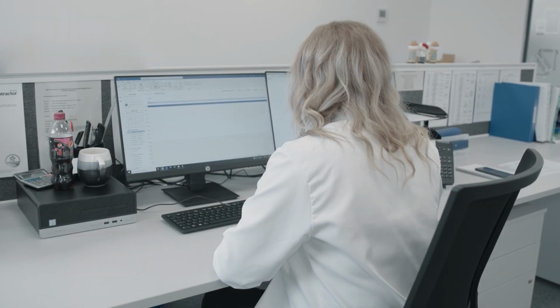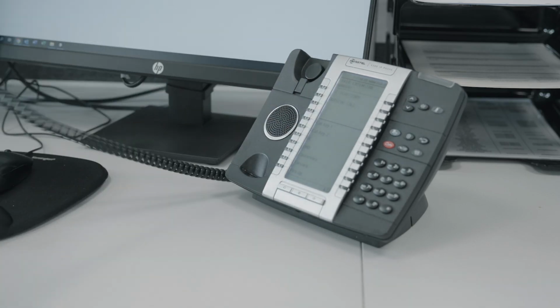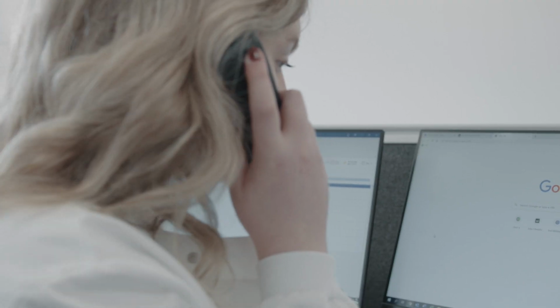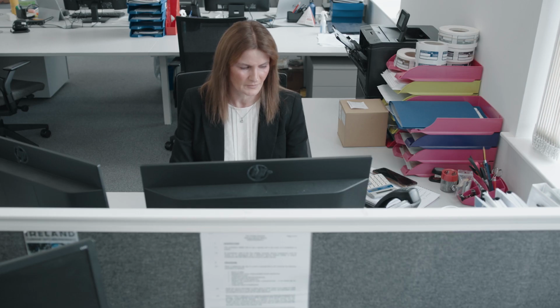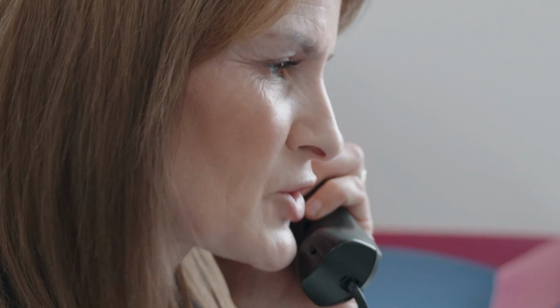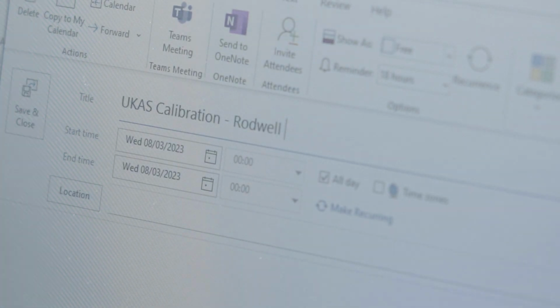Most customers request calibration annually or biannually. Calibration is also advised after a temperature probe replacement, or where maintenance involving the main circuit board has been undertaken, or after an autoclave is being used after a long period of inactivity.